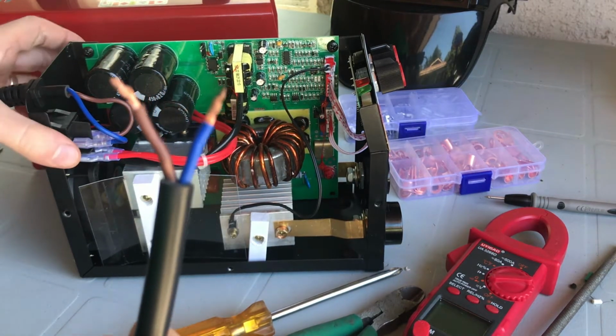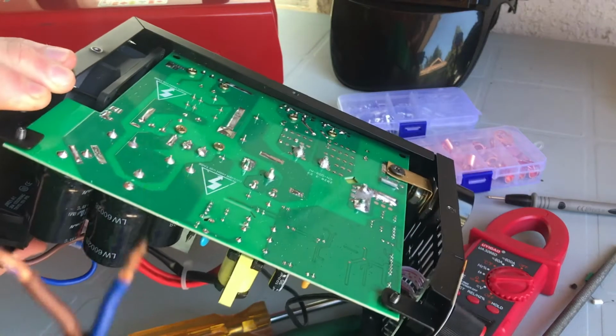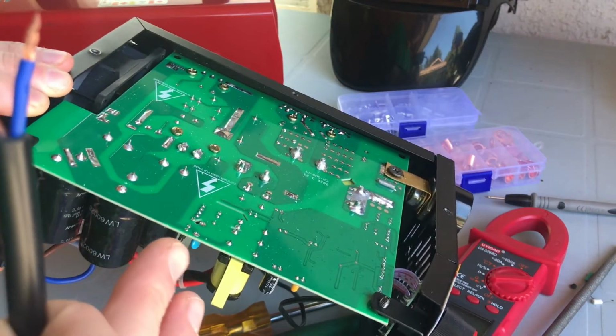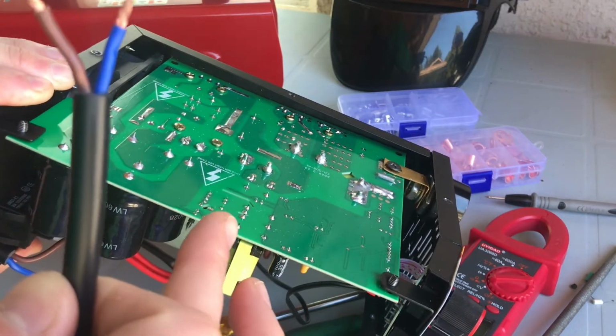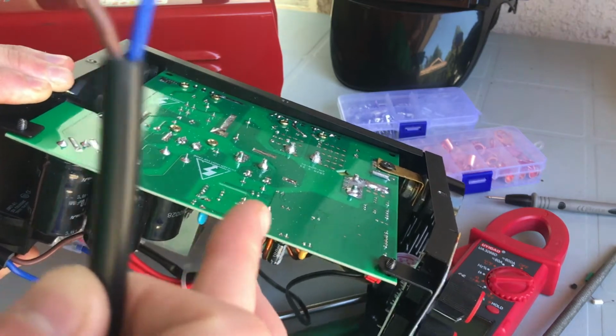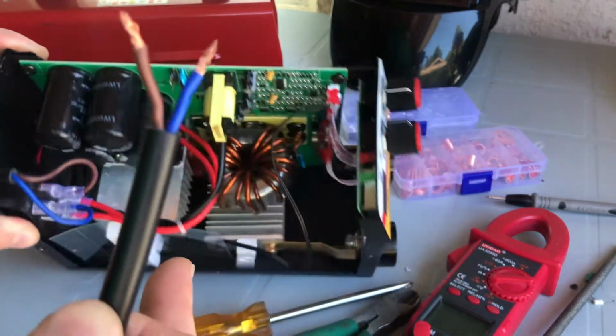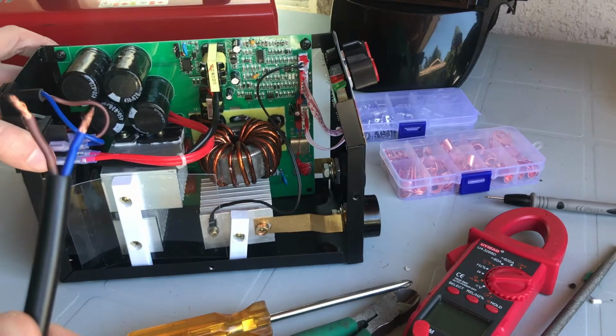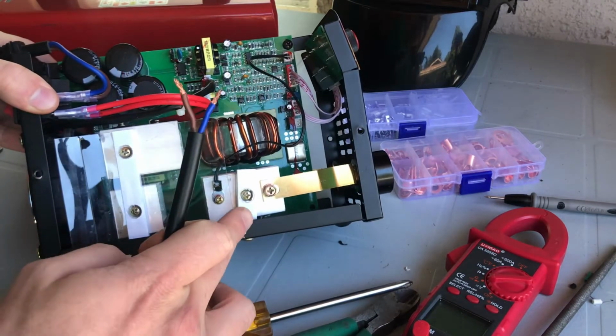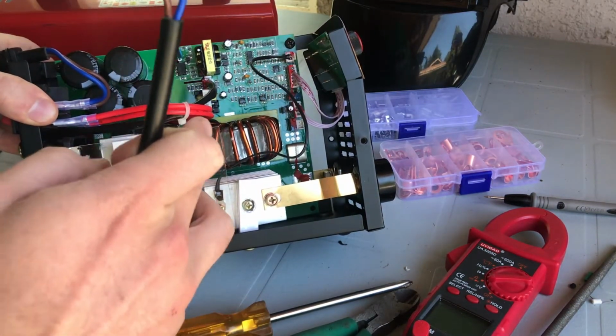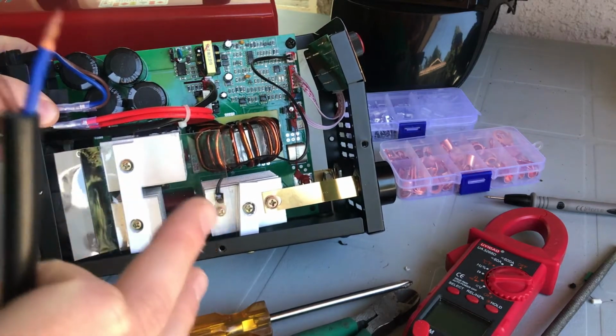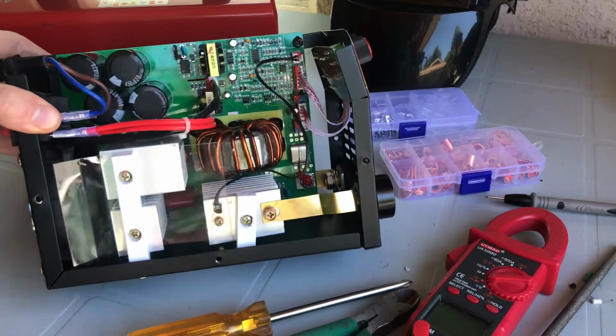Taking a look at the back of the circuit board here, we've got a whole bunch of exposed high voltage contacts. Should these come in contact with the case, this could be an electrocution hazard. It looks like the manufacturer's done some work to isolate all the electrical components from the case, but this doesn't meet North American safety standards.